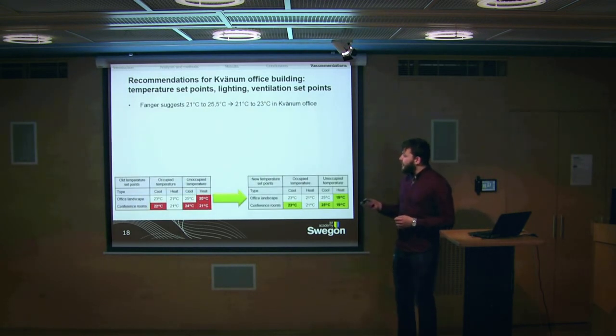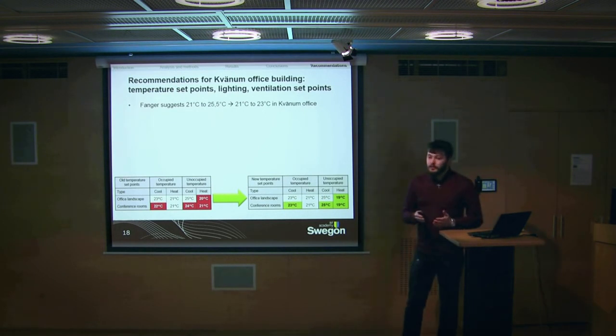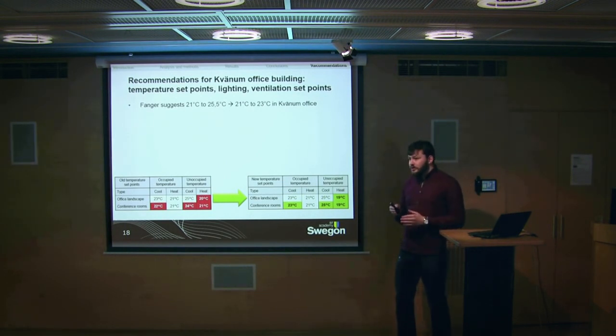So the recommendations for the Kvänum office building are as follows. At the bottom you can see the current set points in the building management system for temperatures, both for when the room is occupied and unoccupied. The red frames are the ones that are changed by 1 or 2 degrees Celsius. So it's just 1 or 2 degrees Celsius. It's not that much, but it makes quite a difference.